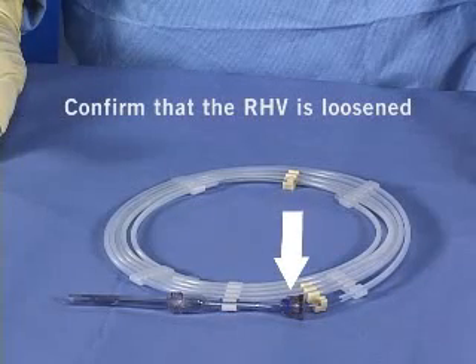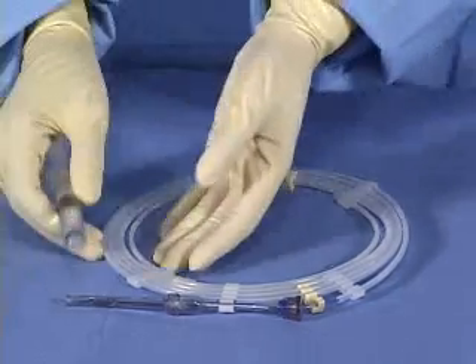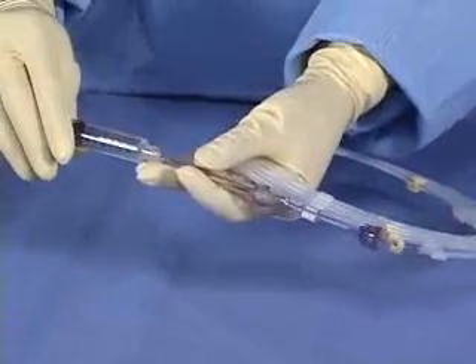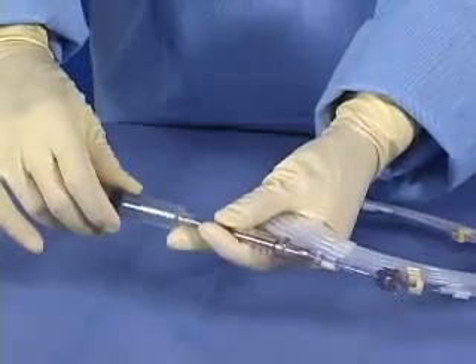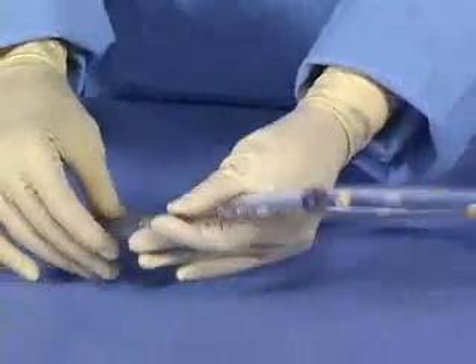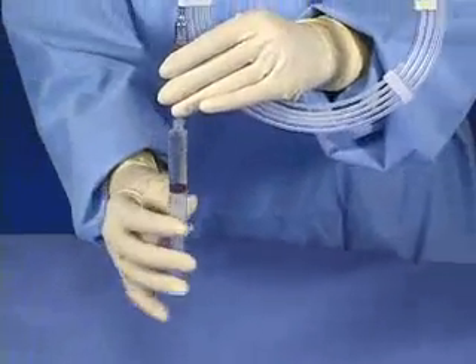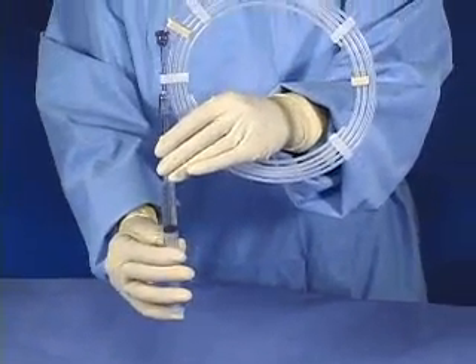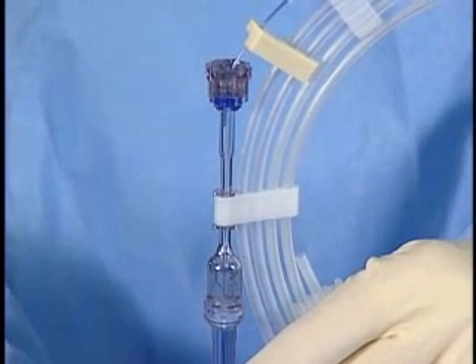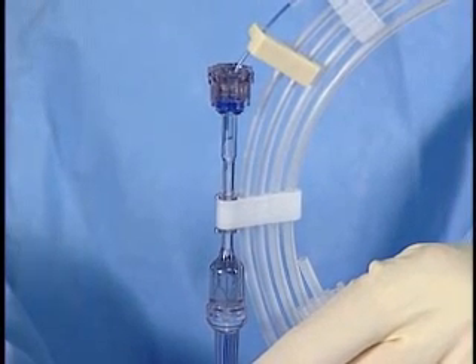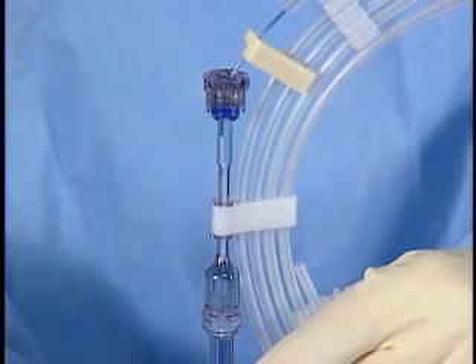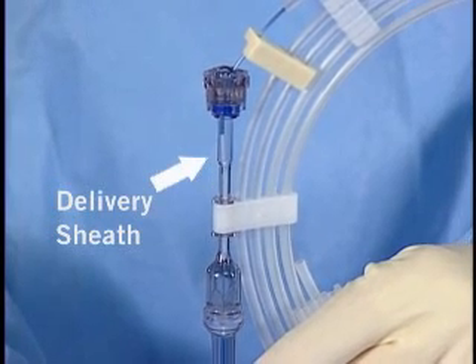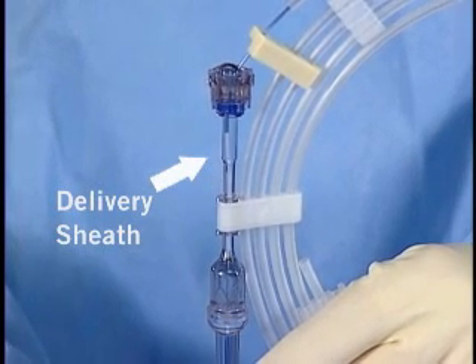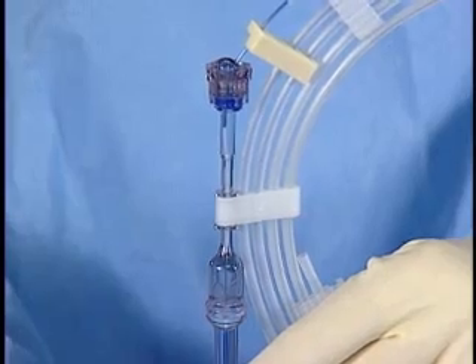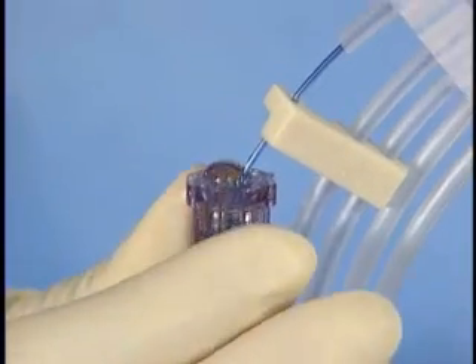Confirm that the RHV on the flush tool is loosened. Attach a 10 cc syringe with heparinized normal saline to the flush tool. Hold the dispenser hoop in an upright position. Flush gently to remove air from the filter basket. Confirm that no part of the light blue section of the delivery sheath is within the valve of the RHV. Then, tighten the RHV.